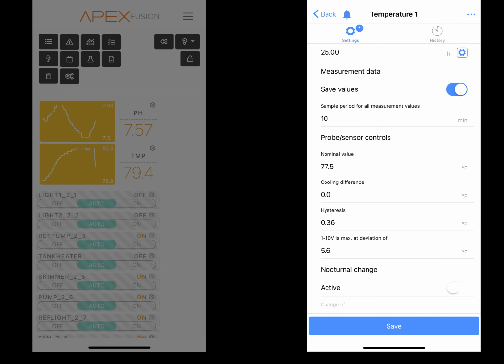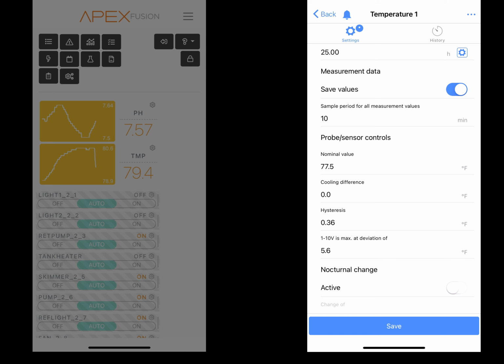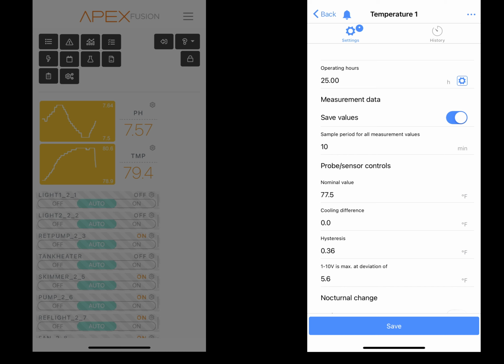Now I need to configure when I want the heater to come on and off. This is where the hysteresis comes into play. The number you enter here will determine how much of a temperature swing you are willing to allow. By default, the value is set to 0.36 degrees Fahrenheit or 0.2 degrees Celsius. I'm going to leave the default value, which means the heater will turn on at 77.3 and off at 77.5 when applied to an outlet. Click the Save button to save the values.